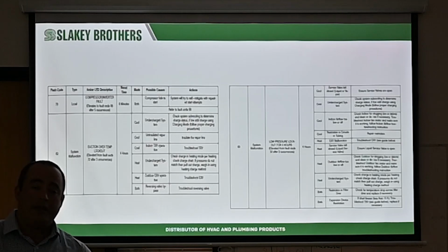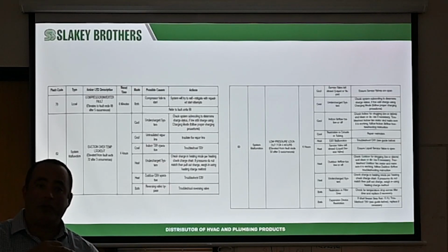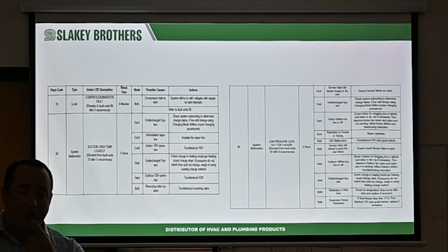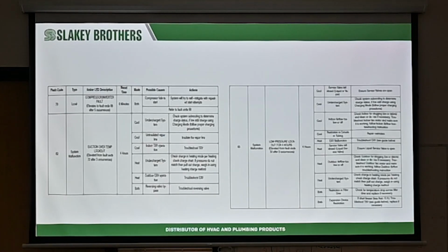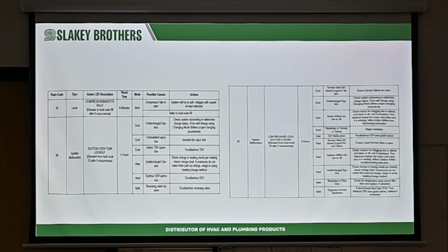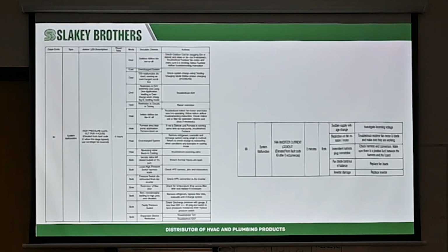step procedure. Sometimes, once you show that your compressor ohms out okay, your condenser fan motor ohms out okay, when it comes to the major failure of it having an inverter fault or a compressor fault, some of these flat out tell you that it's a compressor fault, so replace the compressor first. But on these units, if you're replacing the compressor, you're going to want to replace the inverter board too. It'll bite you in the butt sometimes if you don't.